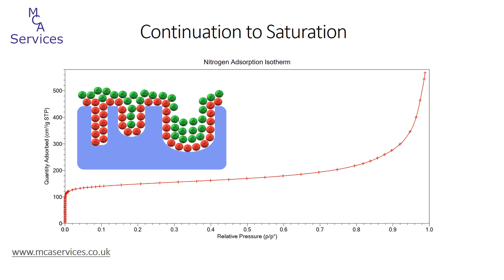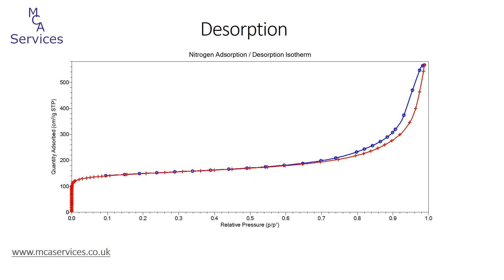The size limit to which pores are completely filled towards saturation depends on a number of things, but we can usually get useful data on pores up to around about 300 nanometres in diameter. Once we've collected the adsorption data, we can repeat the process in reverse, lowering relative pressure and recording the volume of the adsorbate as it's desorbed. The desorption branch of an isotherm is shown here in blue, and we can see that there's hysteresis between the adsorption and desorption branches, which is really very useful when we try to determine the shape of the pores present in the sample.